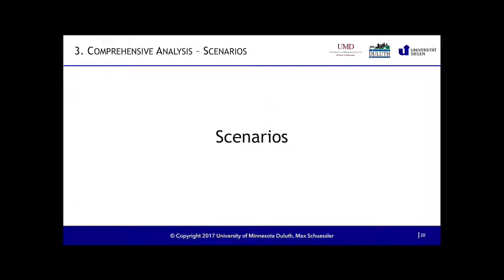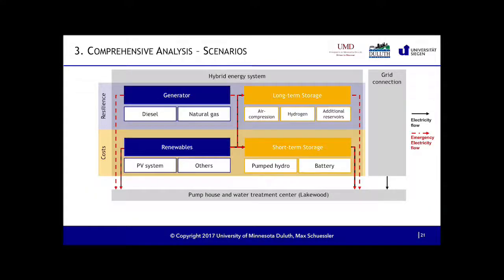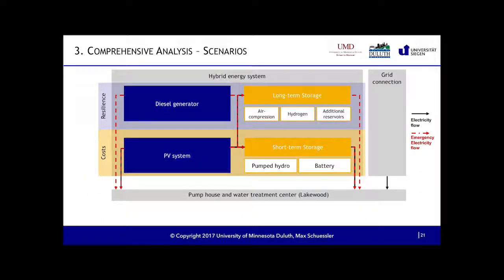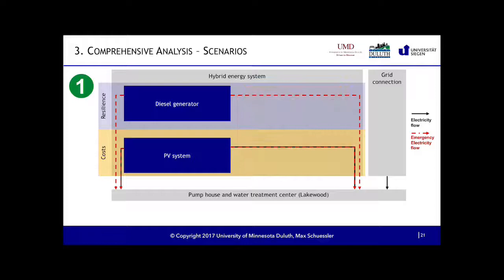And then I combined everything into 3 scenarios that I came up with. This is the picture I showed you already, the picture I started with, and I said that for the generator, probably the diesel generator is the best solution. And for the renewables, the photovoltaic system is definitely the way to go. In my first scenario, I looked at what would happen if I wouldn't use the storage. In this case, I wouldn't have a hybrid scenario anymore, so I would have 2 separate systems, one for the resilience plan and one for the cost-cutting plan, so to say.